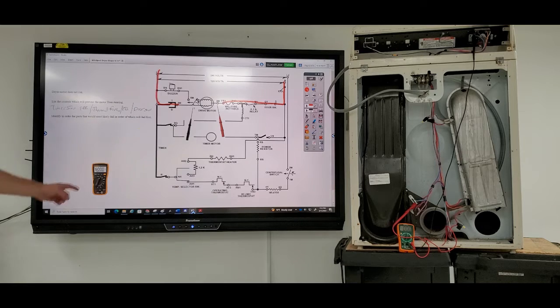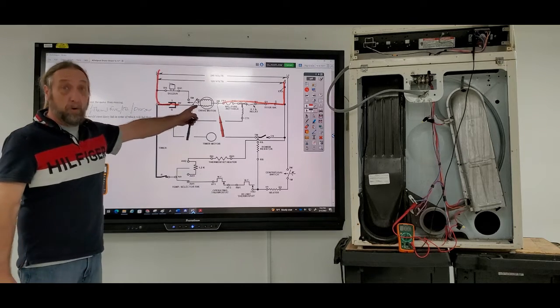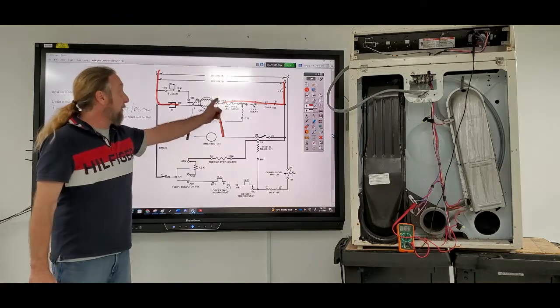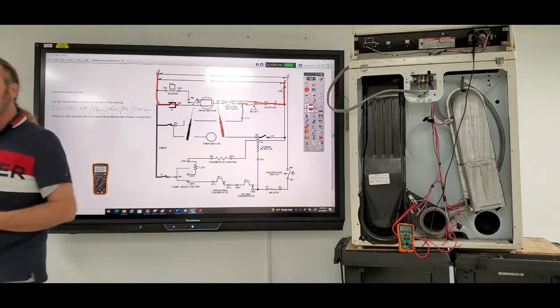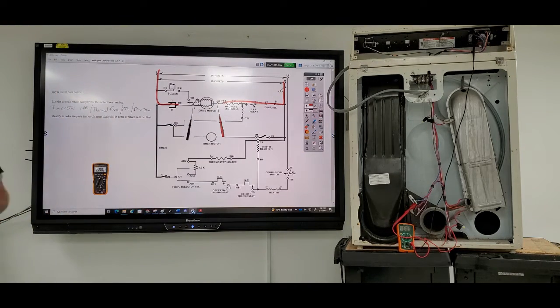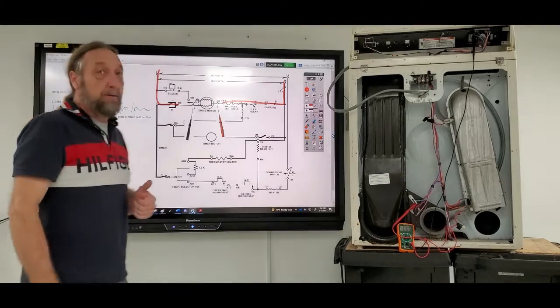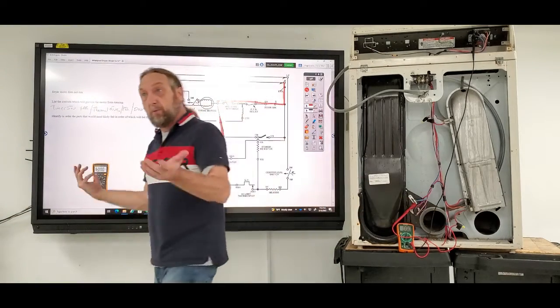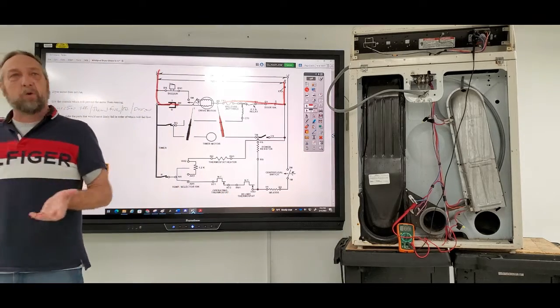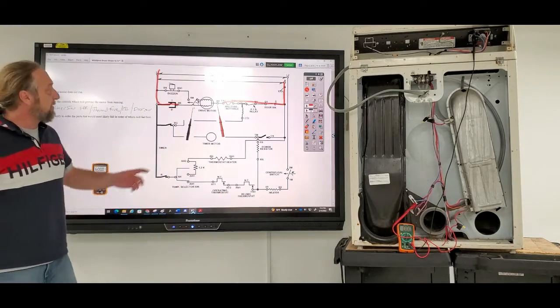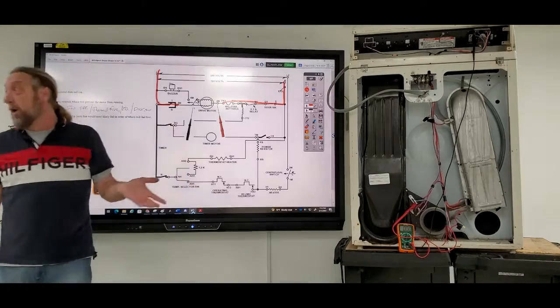Why? Because there are wires that come from the timer to the motor, and from the fuse to the motor, and I could have a bad wire. There's many times that a wire has broken, not always. Like this one here, we got a wire nut on the wire because it was repaired. But there's many times a wire is broken, and the guy says, oh, I got power here, the only thing it could be is the motor.